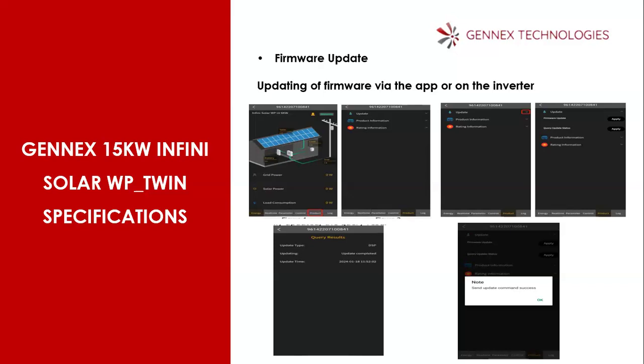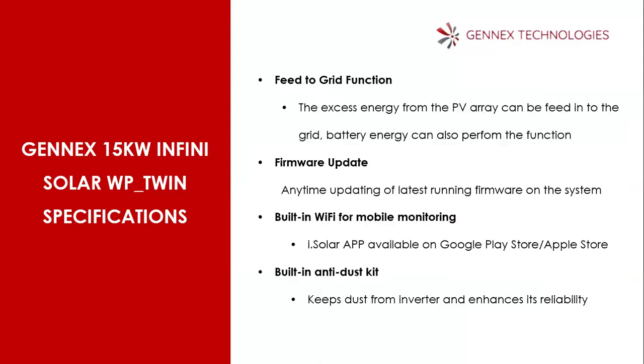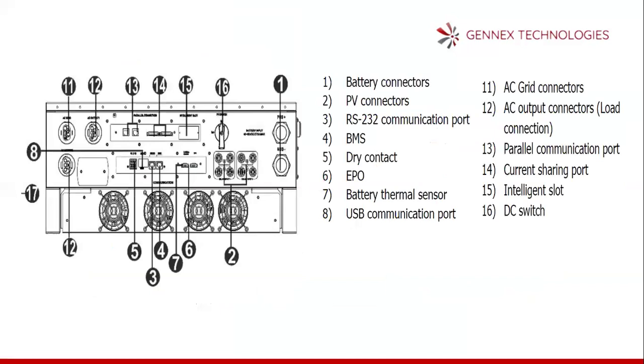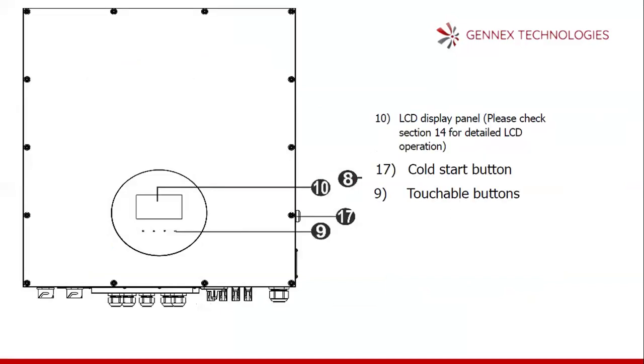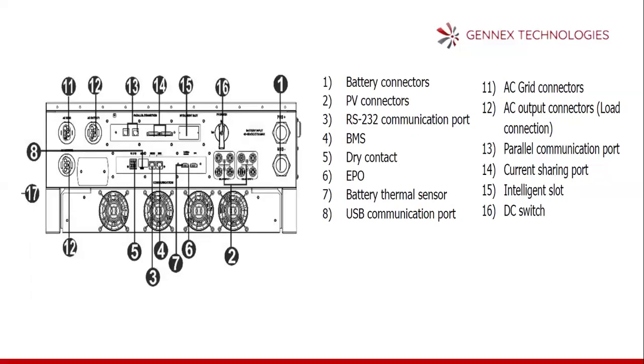So this is the display. You see the display. We have the LCD panel on it, which you have talked about. Then another thing is the cold start button. The cold start button is by the side, which allows the inverter to come up on battery mode, maybe when there is any low voltage on the battery. When you press the button, it will turn on the inverter. Then on the inverter, we have the battery connectors securely put in a compartment to prevent any form of bridging or easy accessibility for anybody.